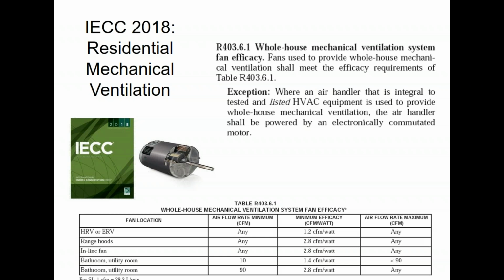But when it's leaky, that causes drafts and things to blow across people, and they compensate for that by jacking up their thermostat. What I want to do is make the house super tight, bring all of the air through one single controlled hole that I can then heat, cool, humidify, dehumidify, and filter, and then bring it to the space. So it's really more of a control thing than anything else. So you have to have the mechanical ventilation.